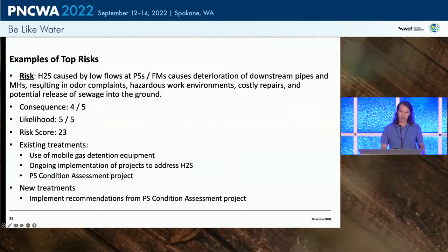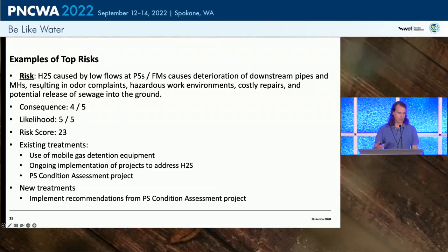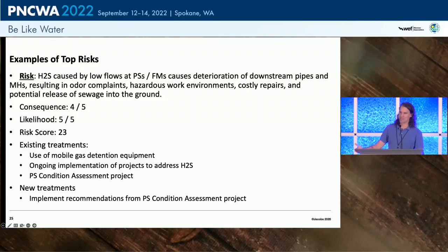Now let's drill into some specific example risks floating to the top. H2S caused by low flows deteriorating the system, resulting in odor complaints and hazardous work environments. We gave that a consequence score of four because of the hazardous work environments, and a likelihood of five because it's a known problem that happens on a regular basis. Overall risk score with the creative math was 23. Existing treatments include mobile gas detection equipment and ongoing H2S mitigation projects. There's a big ongoing pump station condition assessment project, and a new treatment that emerged was: it's one thing to prepare a plan, but let's not forget to implement the recommendations — because plans have a tendency to just sit on shelves.